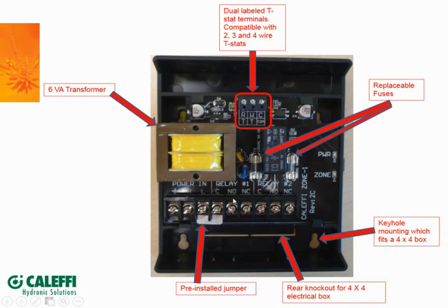We have 2 replaceable fuses, one for each relay. We have keyhole mounting to fit on the 4x4 box as well. This is a rear knockout. If you are going to mount it on a 4x4 electrical box, this is your access to get back into that box. And then we also put in a pre-installed jumper between line and common on that first relay. It's the most common way of doing it. That way you can run power to your system pump right off of that.